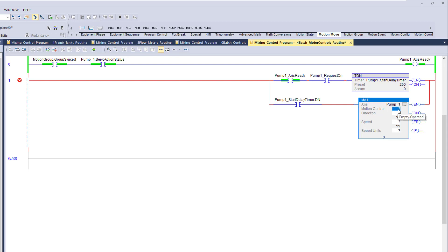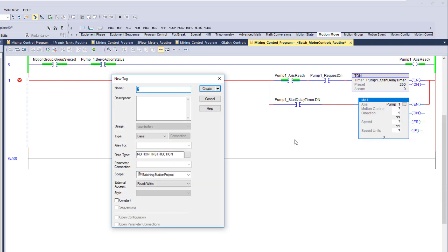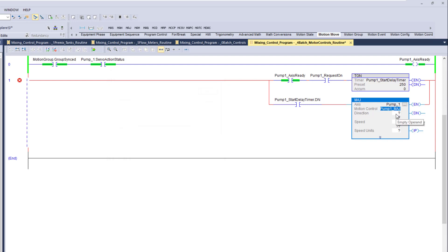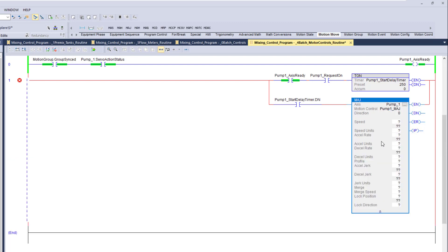The motion control field requires a tag. We need to create a tag for this specific instruction — a MAJ, which is a motion axis jog. We'll call it 'pump one MAJ.' Direction is either zero or one: zero is forward, one is backwards.